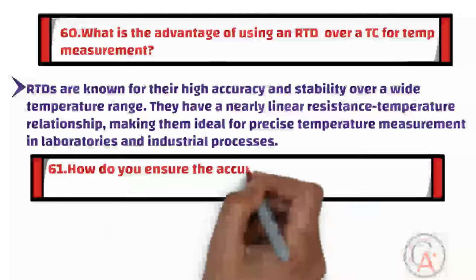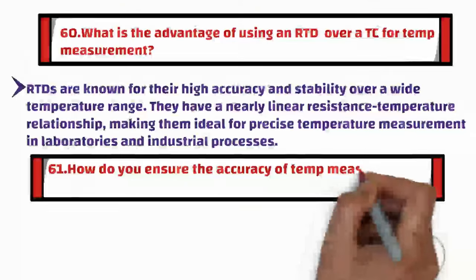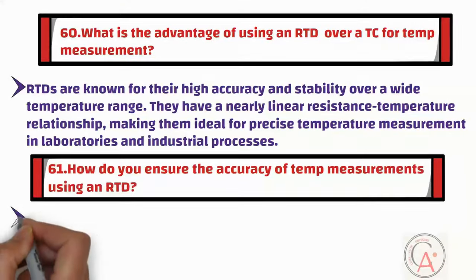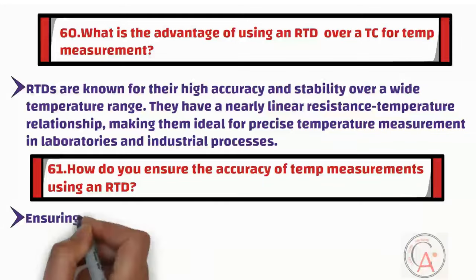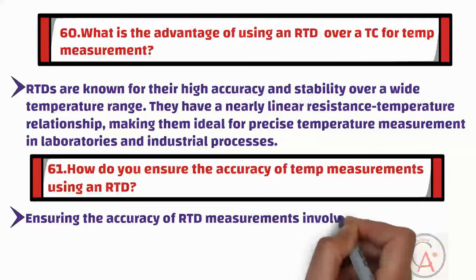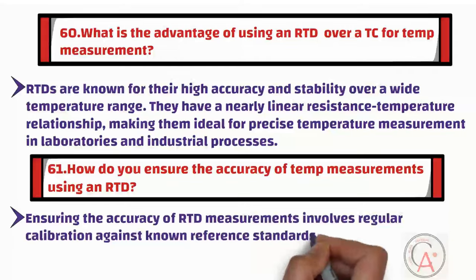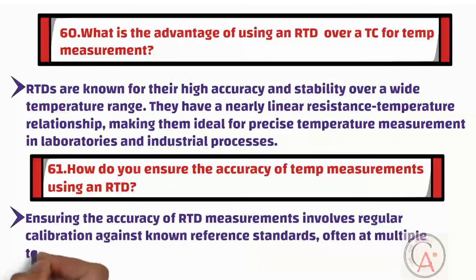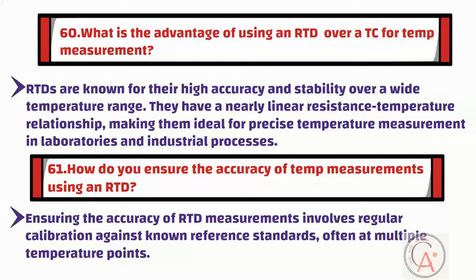Question sixty-one is: how do you ensure the accuracy of temperature measurements using an RTD? Ensuring the accuracy of RTD measurements involves regular calibration against known reference standards, often at multiple temperature points. The use of precision resistors in the measurement circuit and proper lead wire compensation are also essential.